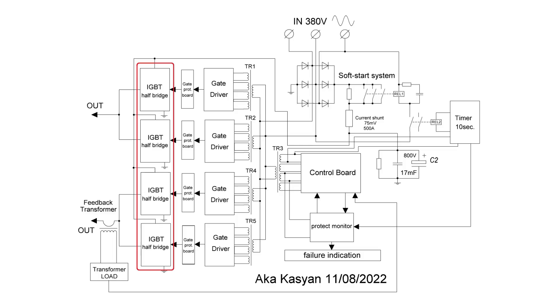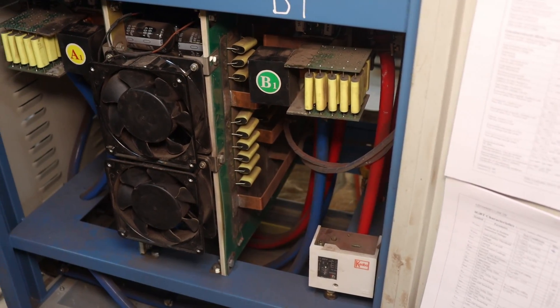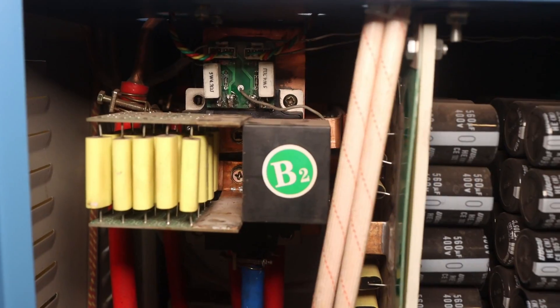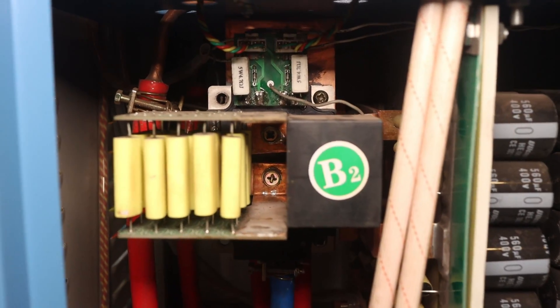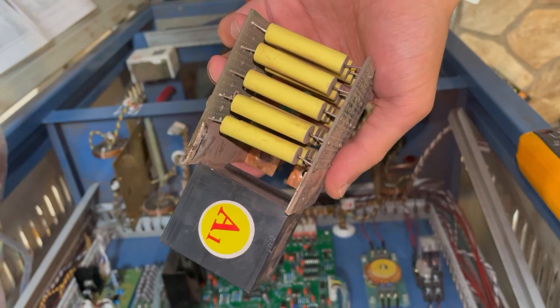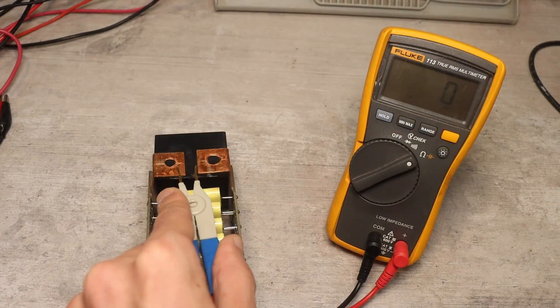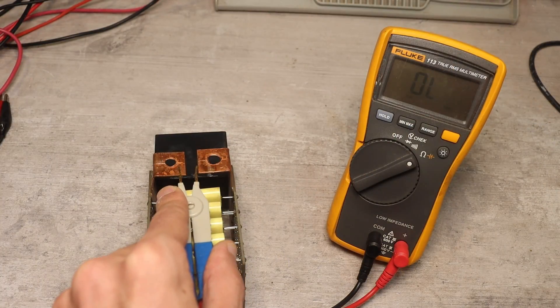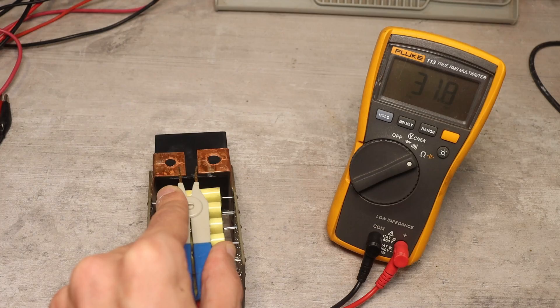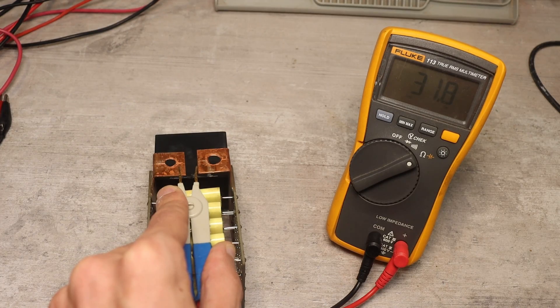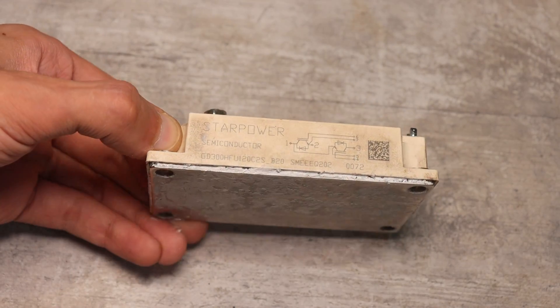Power switches. Let's start, perhaps with the damper capacitors that were on the power outputs of these switches. This is a high voltage bank of capacity about 30 microfarads. All 4 banks are fully functional.